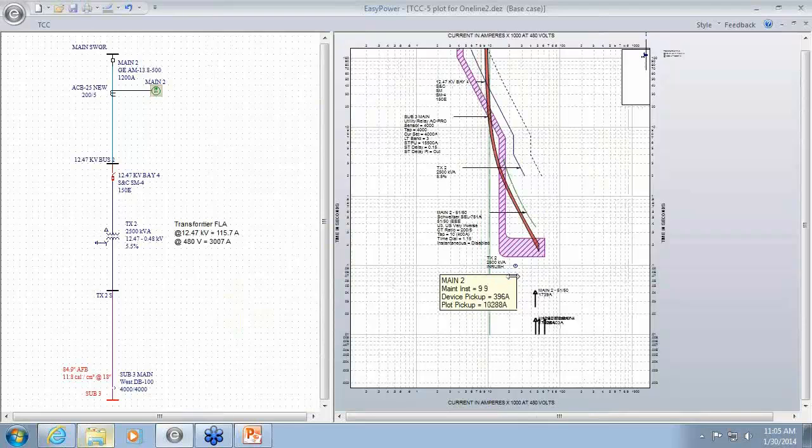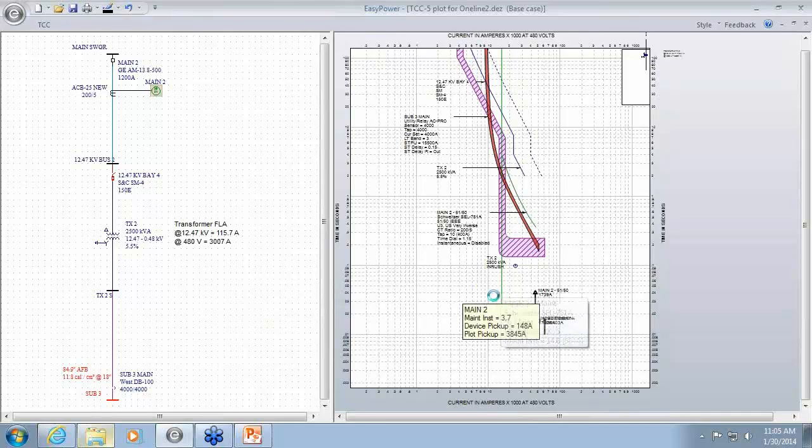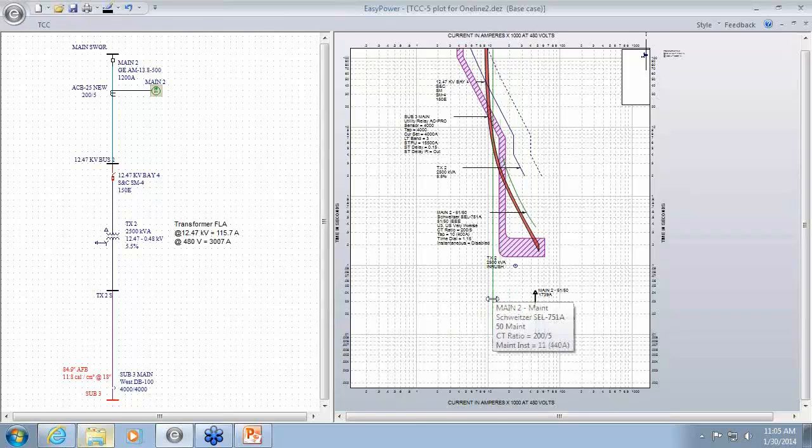I don't know if that's a realistic setting, but as long as it's below this, usually, since we're dealing with safety, I'd rather be a little bit further away from the arcing current, because it's still a probability as far as how that number has been derived.